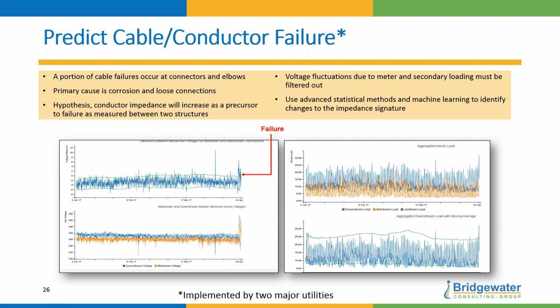You see some examples here of a plot. I don't want to call it just a voltage plot, because you're looking at meter voltage and trying to extrapolate up to 12 kV. So you have to take out a lot of factors, including the loading on the meter. What you're trying to do is normalize it to say what's happening at 12 kV, even though you're reading at 240.